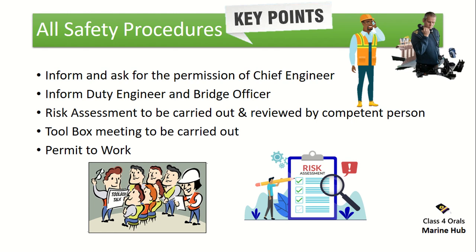Third, a risk assessment is to be carried out and reviewed by a competent person. Fourth, a toolbox meeting should be carried out before proceeding for the maintenance. Fifth, the permit to work should be filled — it is an official document which has to be duly signed by the responsible person.